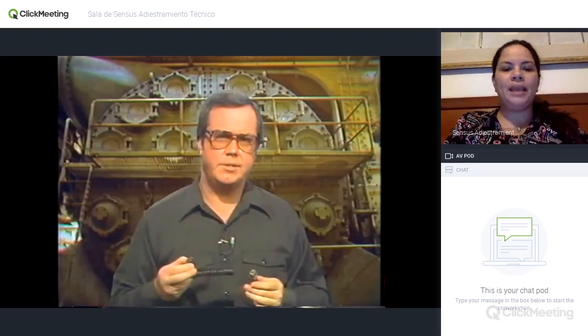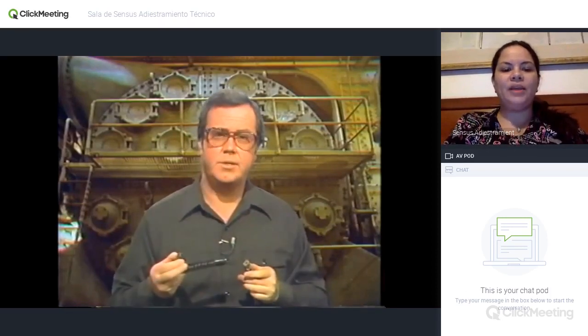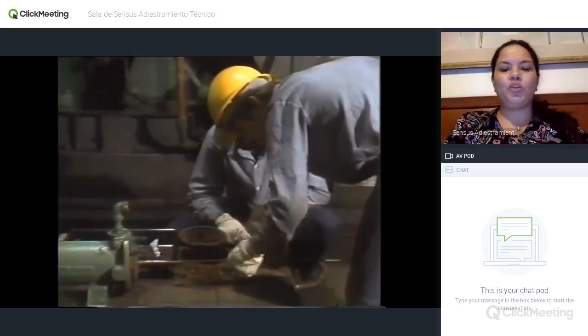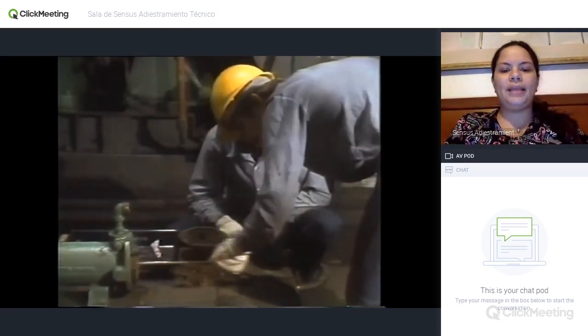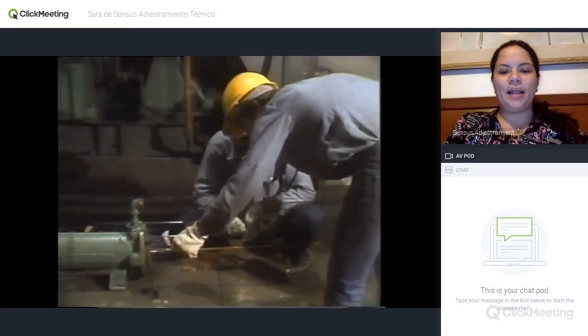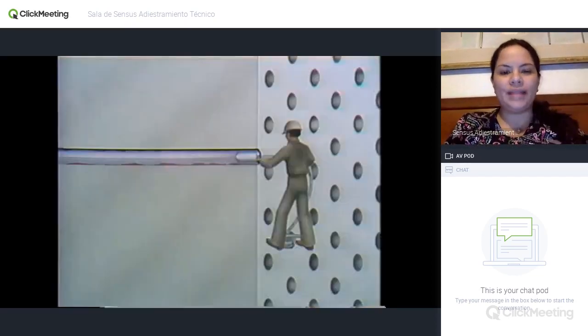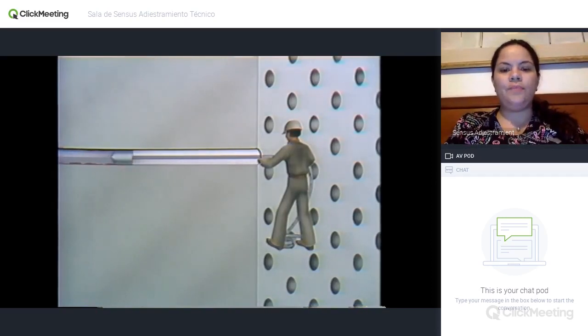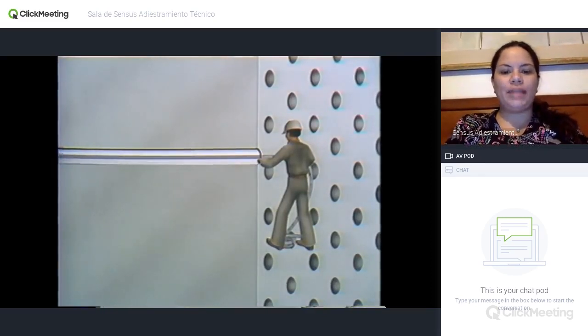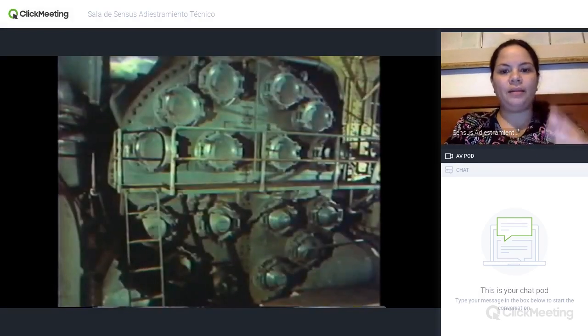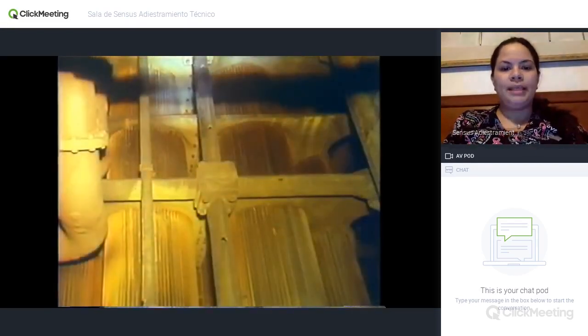The one you choose depends on what you're trying to get out, and that depends on what's going through the heat exchanger. Another way of cleaning tubes is rodding. It's the elbow grease version of shooting tubes and is practical on small heat exchangers like a small oil cooler. And there are also devices like plumber's snakes used to clean drains and sewers. They remove the toughest stuff with a rotating scraper on a flexible cable. In large heat exchangers, tube bundles can be pulled out so the outside of tubes can be cleaned. Corrosion, scale, and deposits can be brushed off with wire brushes.